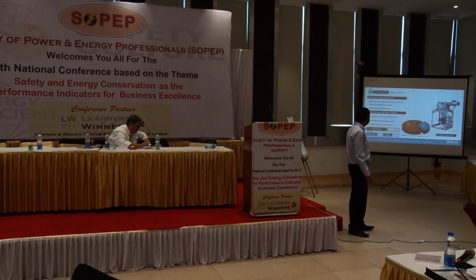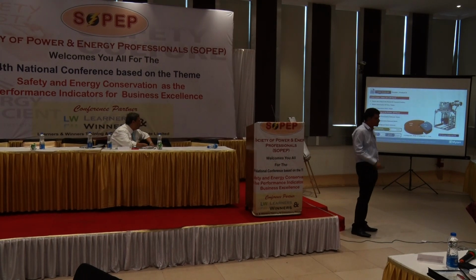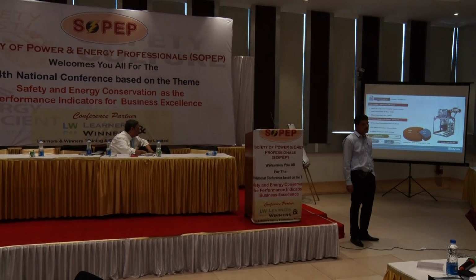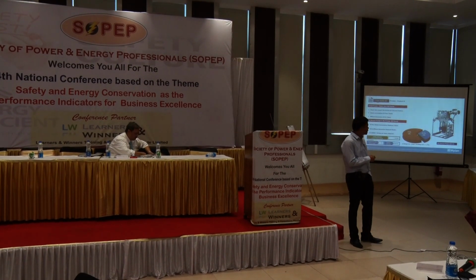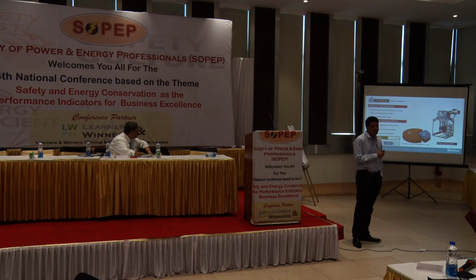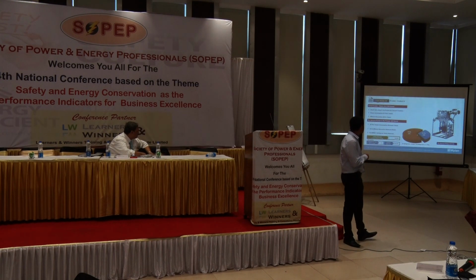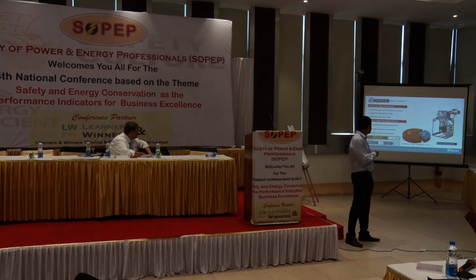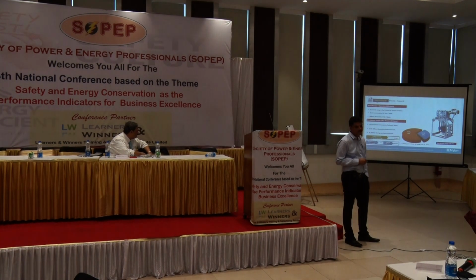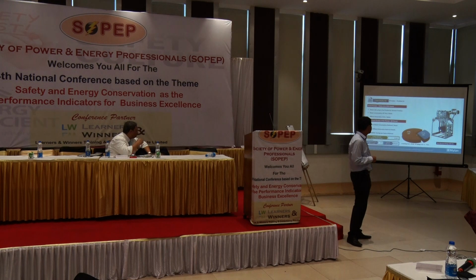So this is also the same thing. A 5-stage steam jet, high vacuum jet, we have replaced with the dry vacuum pump, and the time cycle has reduced from 100 hours to 50 hours. The investment is 15 lakhs and payback is 8 months. The savings is 54 lakhs in this system, because the productivity has increased and efficiency has increased, sir.